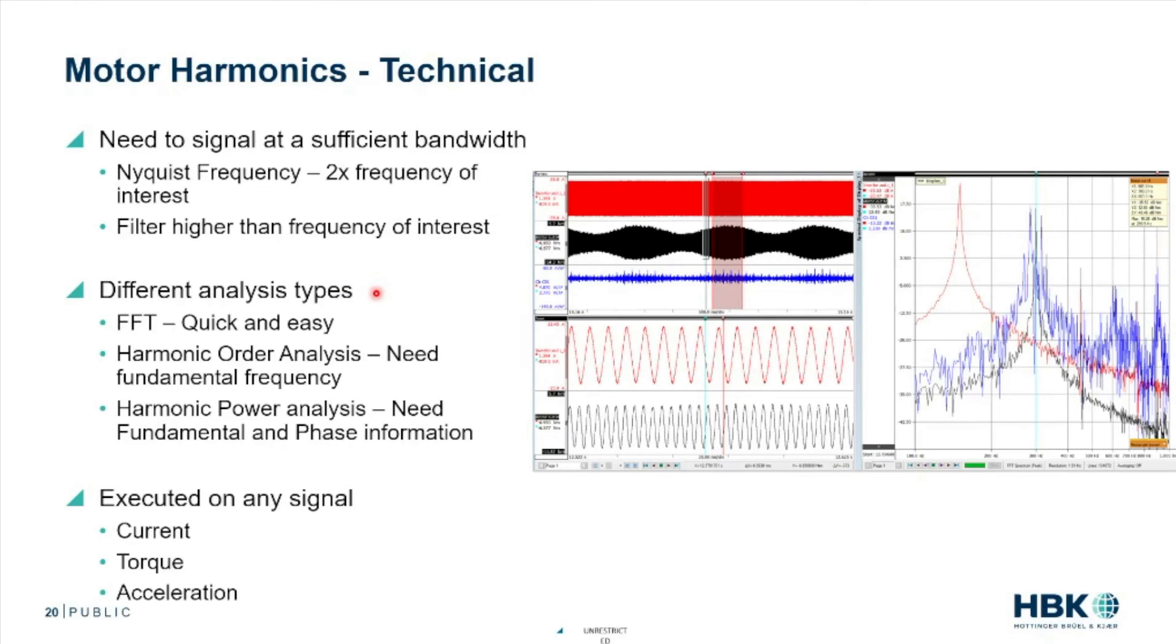We have a variety of different analysis types we can do. All of them do rely off of kind of the Fourier analysis. But we have the FFT, which is featured here. It's really quick and easy. But it might not give us, it might actually give us too much information typically. We could do a harmonic order analysis where we do it based off the speed of the machine. But in this case, we need to know about the fundamental frequency. And I'll touch on each of these a little bit more.